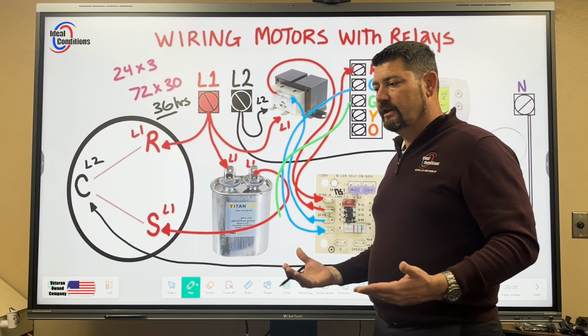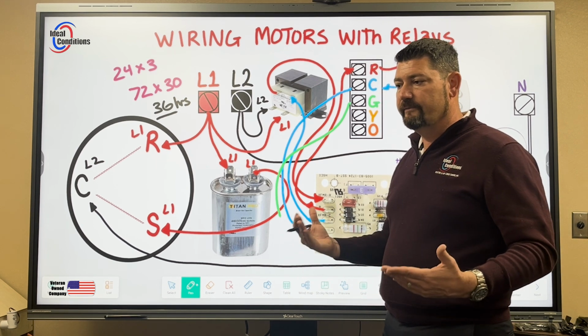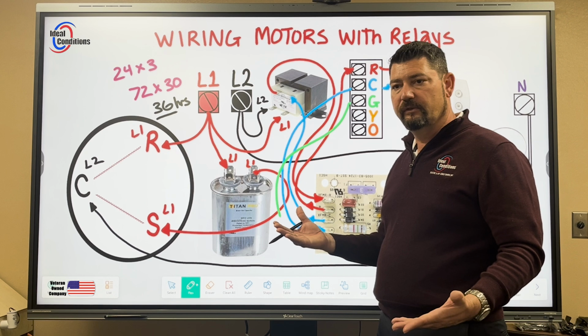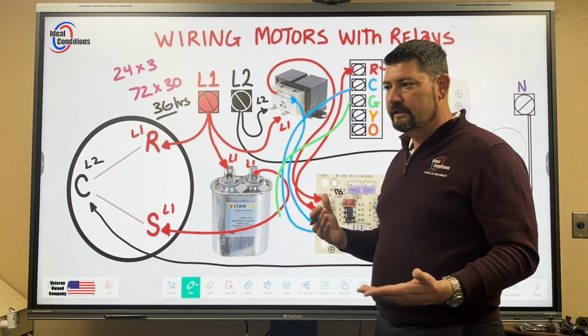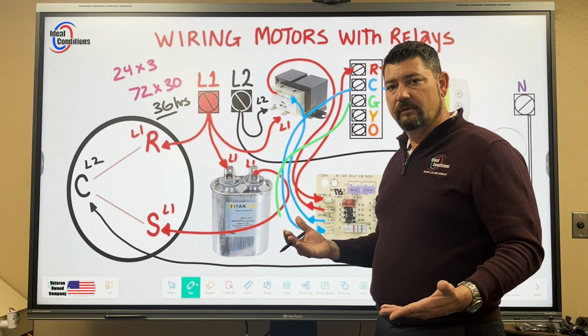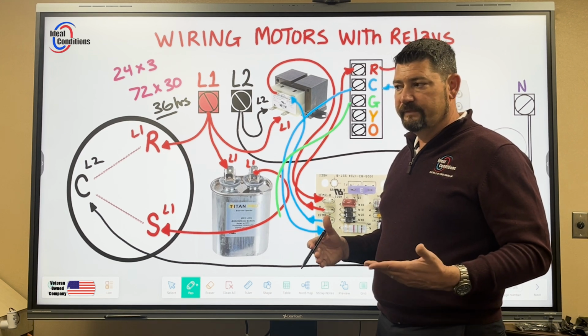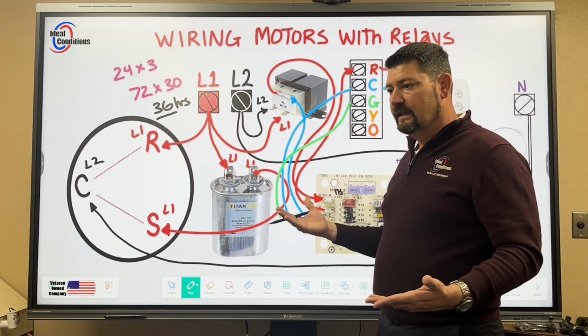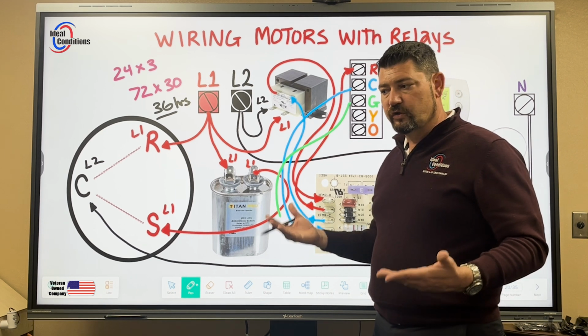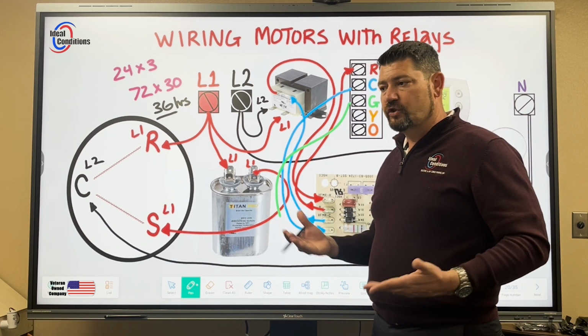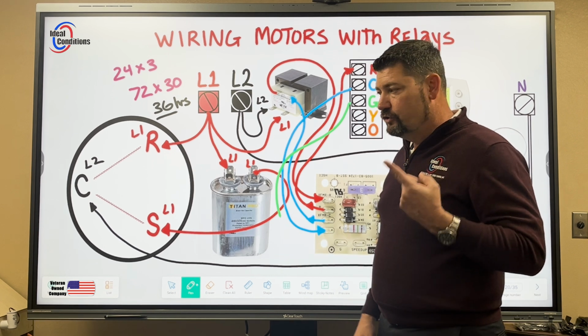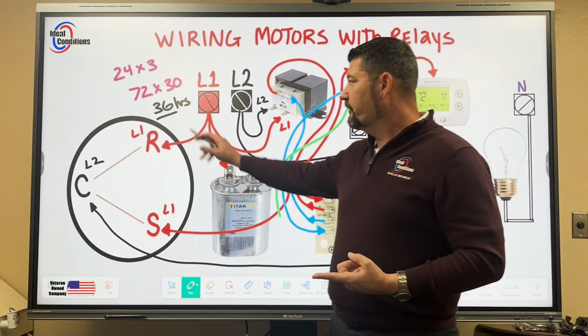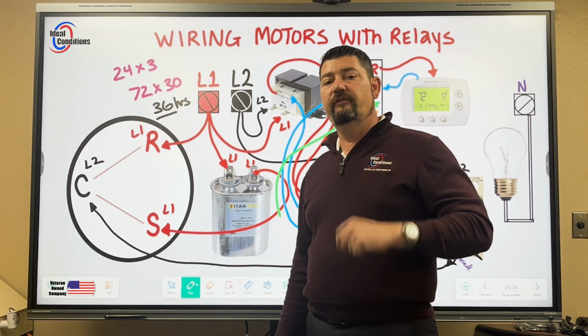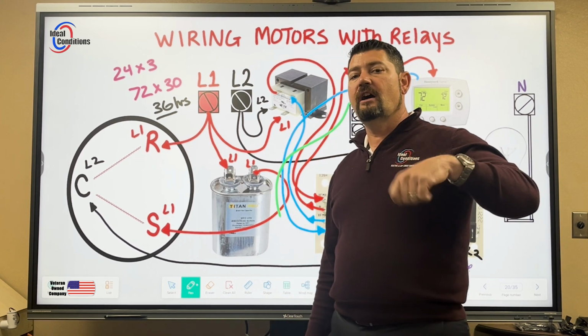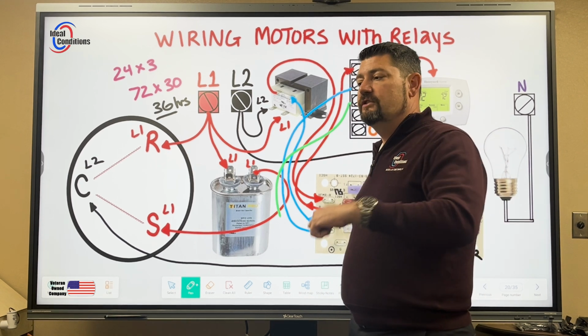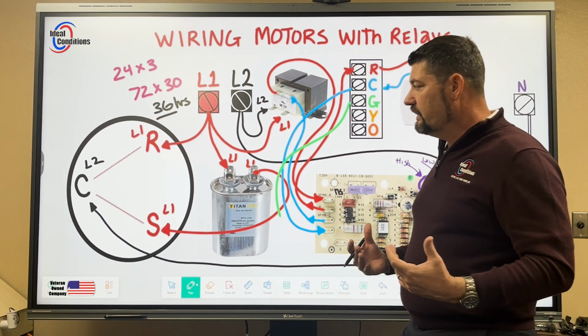But when you're talking about a compressor and a condenser fan motor that's probably running around 12 to 16 amps, in conjunction with the blower motor that's running another 1.5 to 2 amps, okay, you're totaling between 14 to 18 amps of electricity to transfer heat. And now you're transferring heat for 2 amps of electricity over 36 hours. That is the efficiency that they're talking about. So it's not just the comfort that it gives you, it is the efficiency. And so that's very neat.